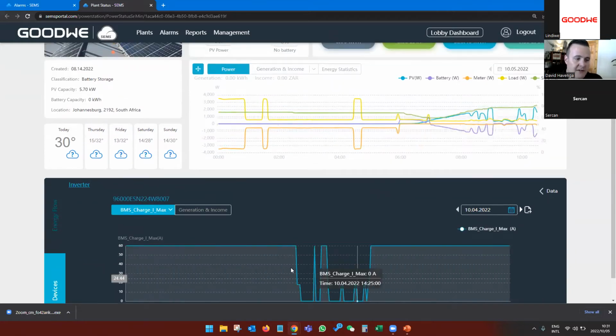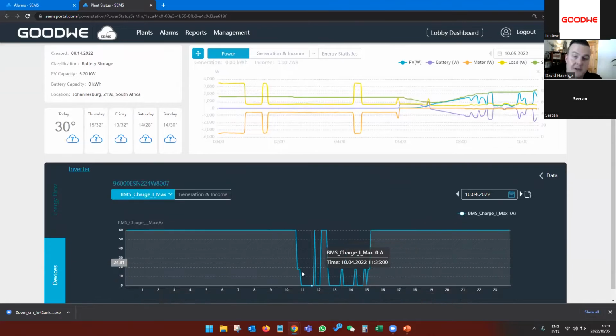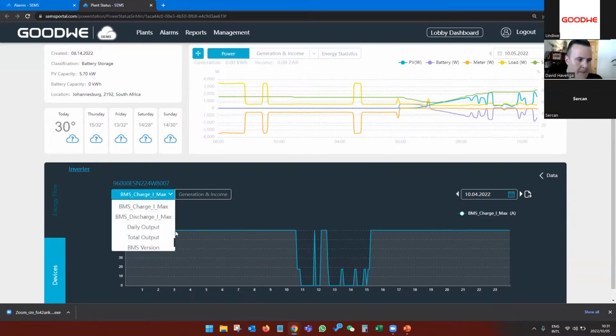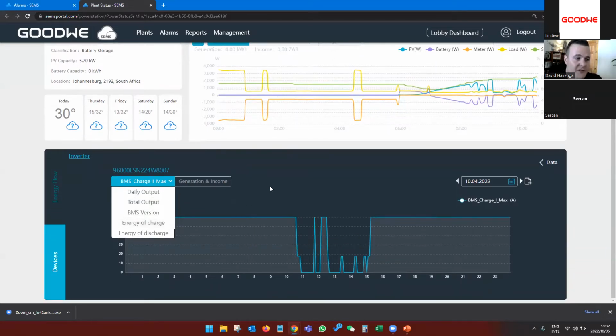full. So when our battery is getting full, then it's going to stop the discharge or stop the charging of the battery. So if your batteries aren't charging full, you can always come here and have a look and see, is my BMS limiting my charge? If the BMS is limiting the charge, it could be a battery-related problem. And then same we have the discharge Imax. Also note the charge Imax will also lower if your batteries are very cold. So based on the batteries, when your battery is normally below 10 degrees Celsius, your charging current will go half. So yeah, we can see a lot of information which is available in fault finding different scenarios of our inverters.